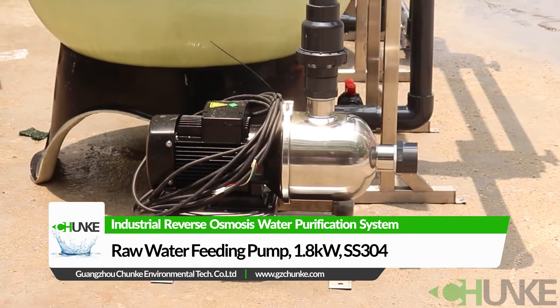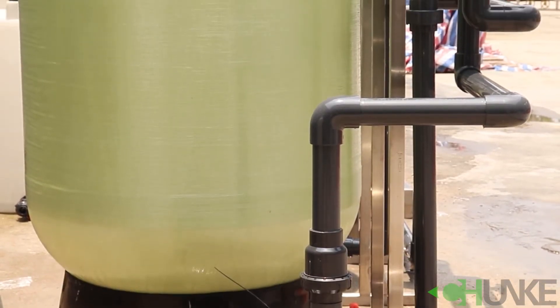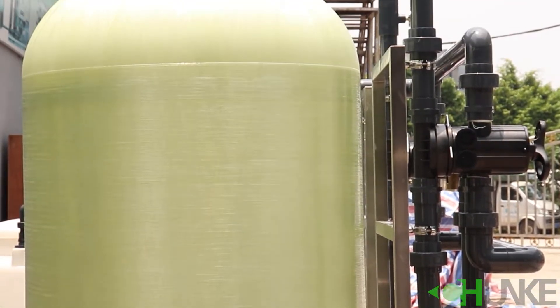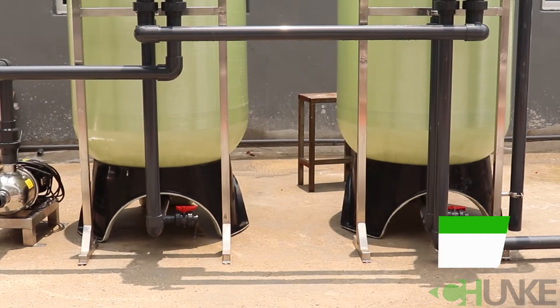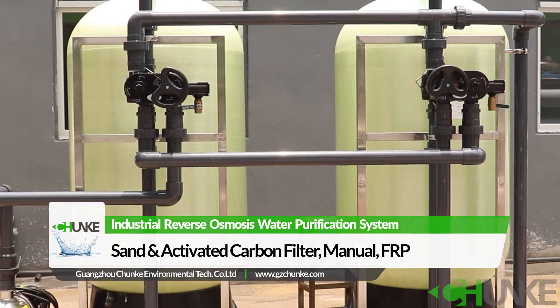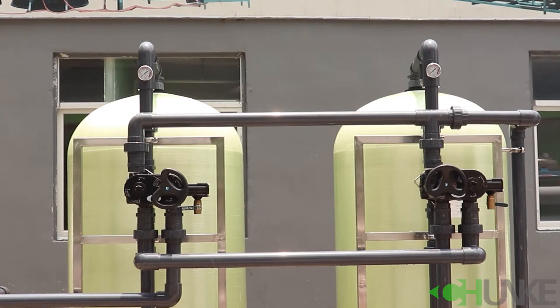The system starts with a raw water feeding pump, which feeds water to the pre-treatment tanks. They are sand and activated carbon filter tanks. The sand filter removes small particles, while the activated carbon filter removes chlorine, some organic compounds, and odor.